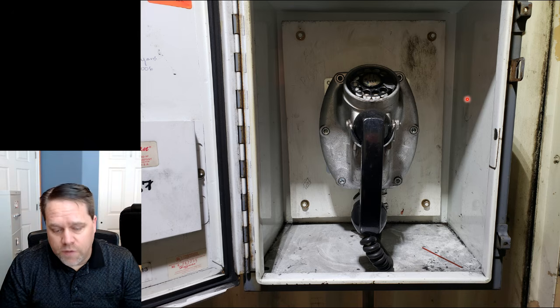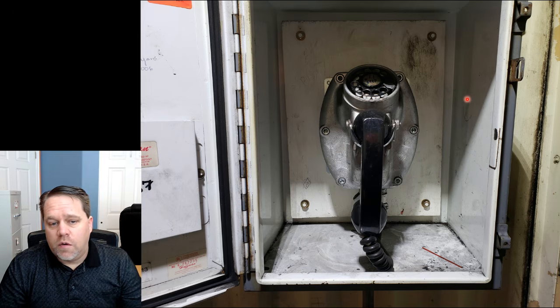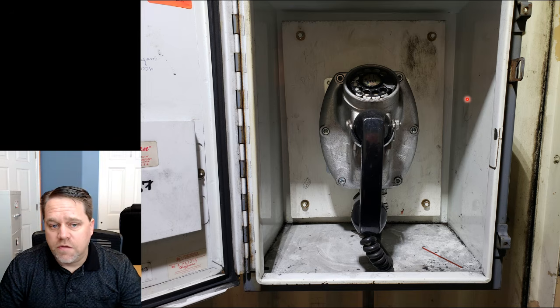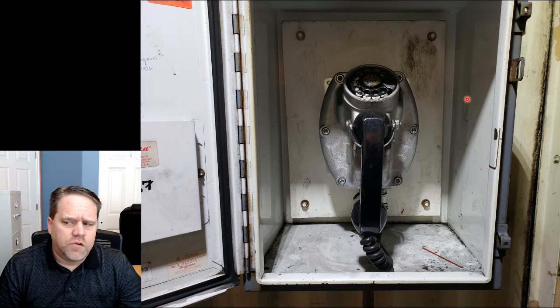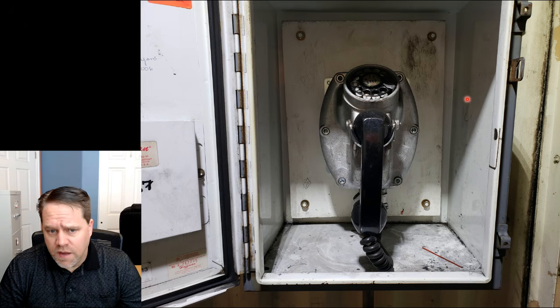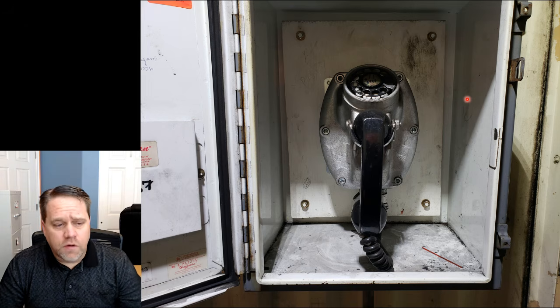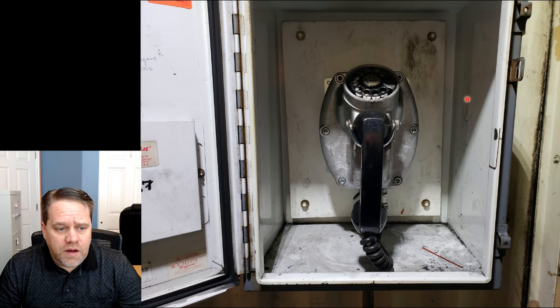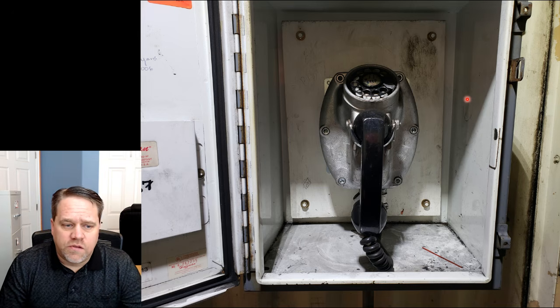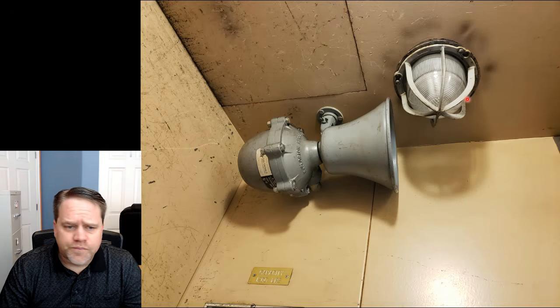It may be low voltage, but there's still enough power even in a telephone circuit that you could ignite the surrounding environment. Section 502.150 in the NEC says that even low voltage equipment needs to be rated for the location in which it's installed if it's in a hazardous location.